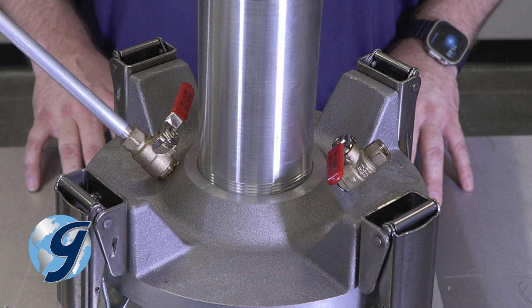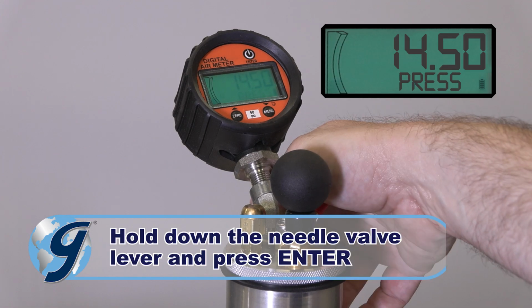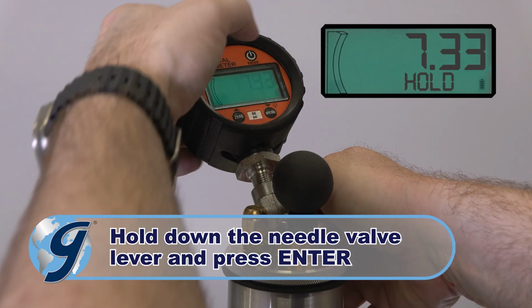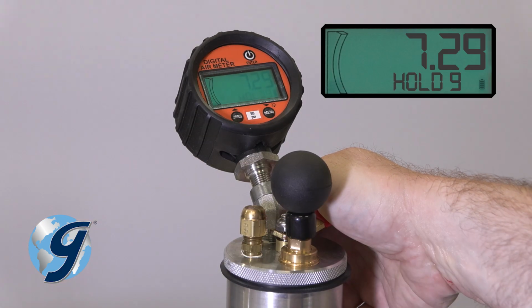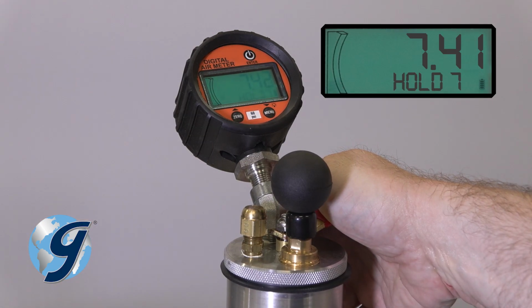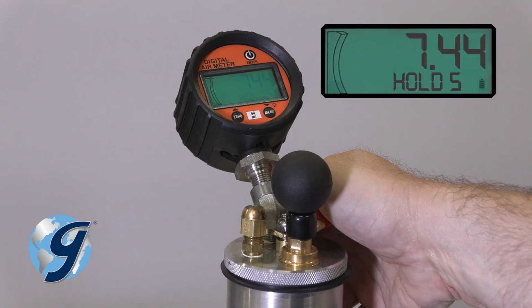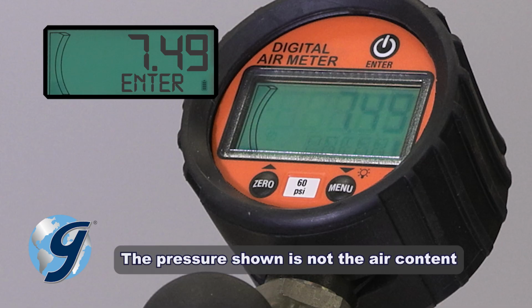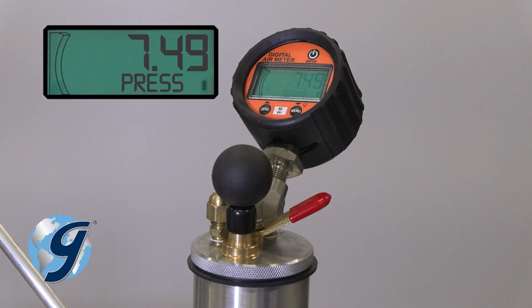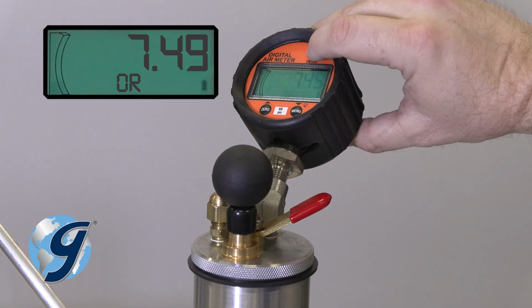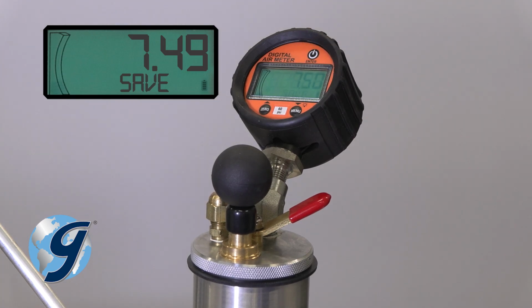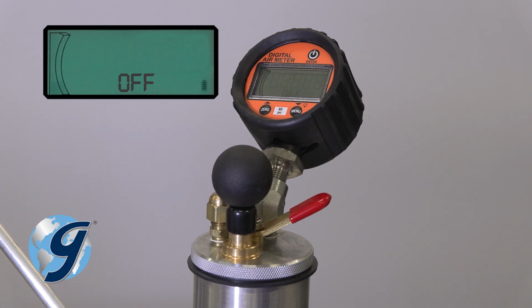Now, when prompted by the gauge, hold down the needle valve lever and press Enter. The gauge will perform a 10-second countdown, then will indicate when to release the lever. The pressure will be shown on the gauge. Finally, press Enter to save calibration or hold the menu button to abort and not save the calibration. Then the gauge will automatically turn off.